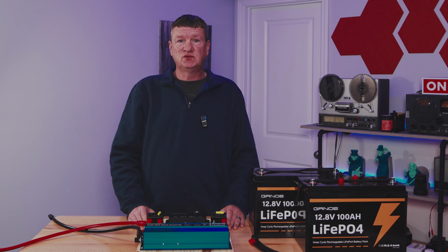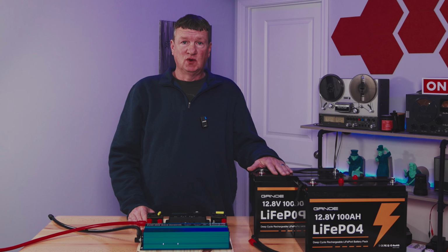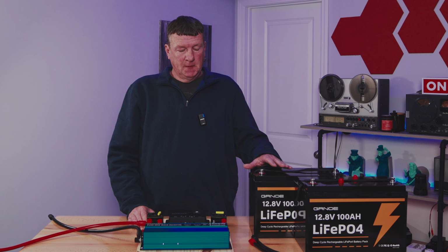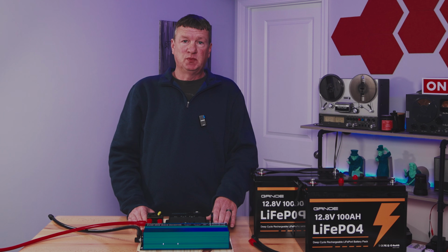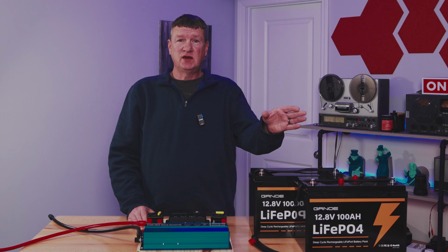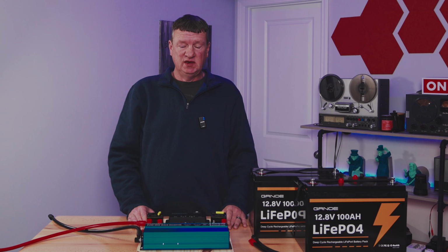So let me explain. The radios we're using require 13.8 volts for maximum power output. The batteries are only providing 12.8 volts. By the time you run 50 feet of 8 gauge wire from this board to where the radios may be placed, you'll have a voltage drop across that line of about 1.4 volts, giving us 11.4 volts to the radios. So they're not operating at their maximum.